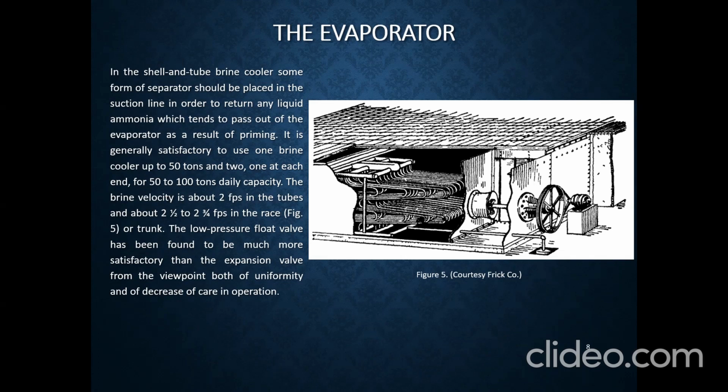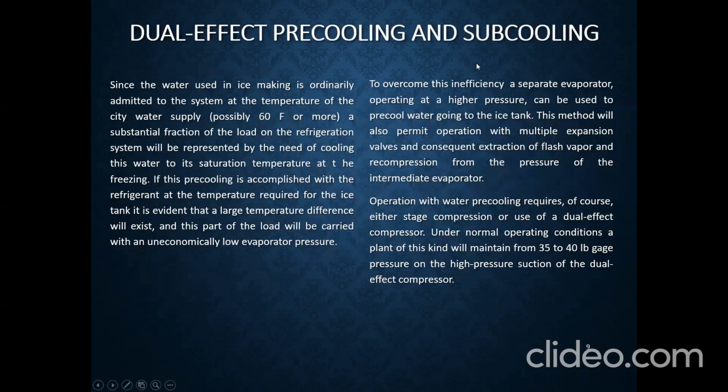figure 5. The low pressure float valve has been found to be much more satisfactory than the expansion valve from the viewpoint both of uniformity and of decreased care in operation. Next, dual effect pre-cooling and subcooling.